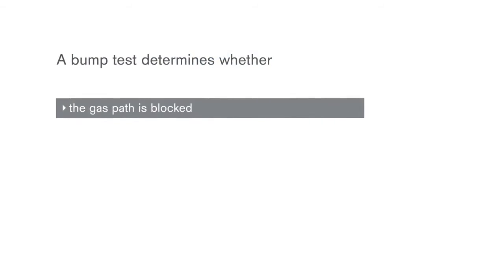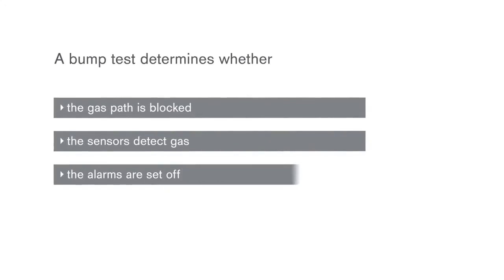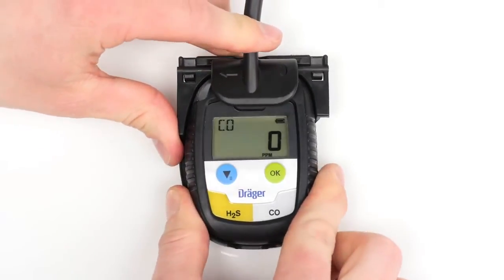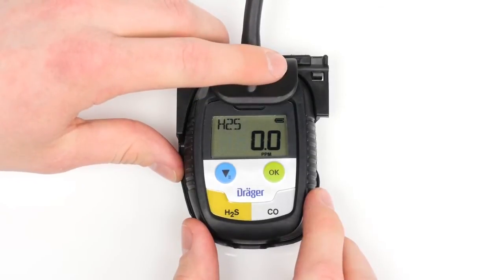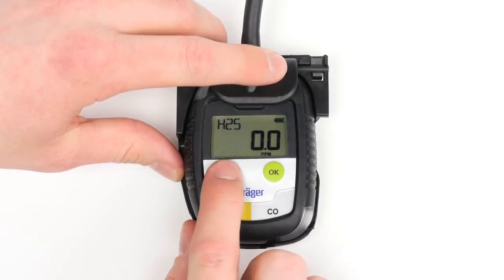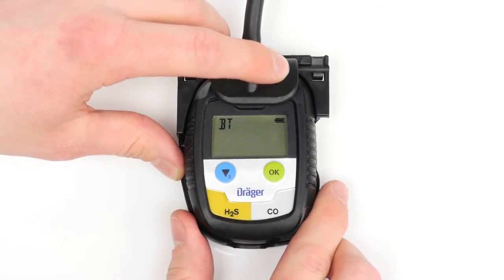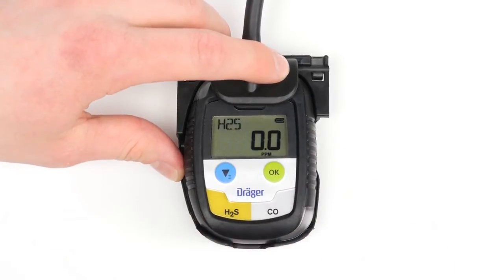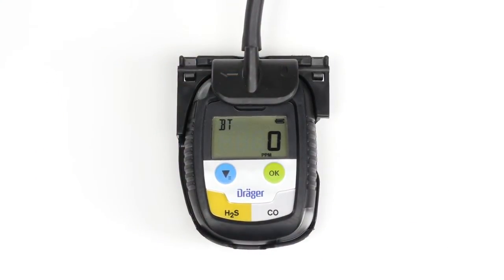A bump test determines whether the gas path is blocked, the sensors detect gas, and the alarms are set off. To conduct a manual bump test, attach the device to a calibration adapter and connect the adapter to a test gas cylinder. Press the blue menu button three times in a row, then press the OK button to start the test. The BT symbol will appear on the display. After a few seconds, the Draeger Pac will activate the alarm. Remove the device from the calibration adapter. As soon as the bump test is completed, the alarm stops and OK will appear on the display.